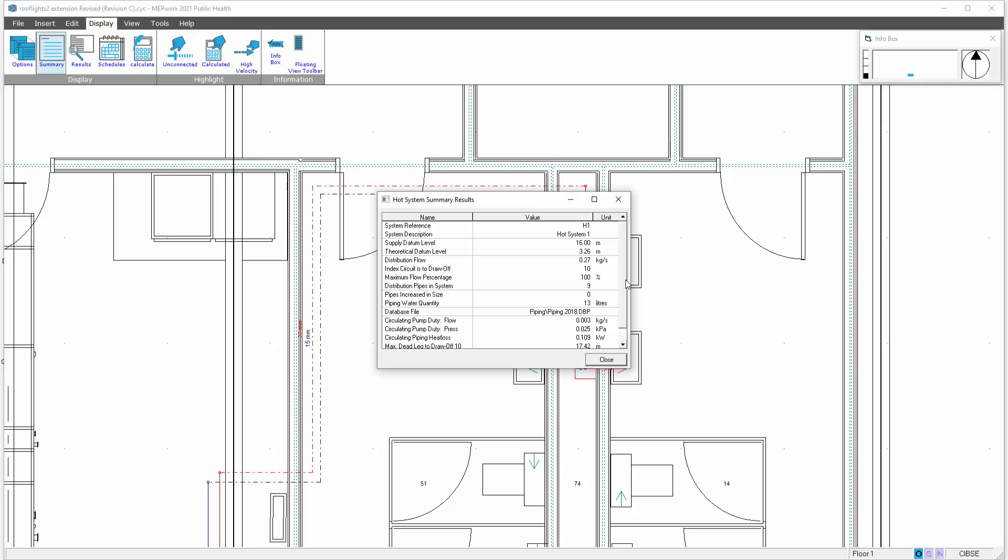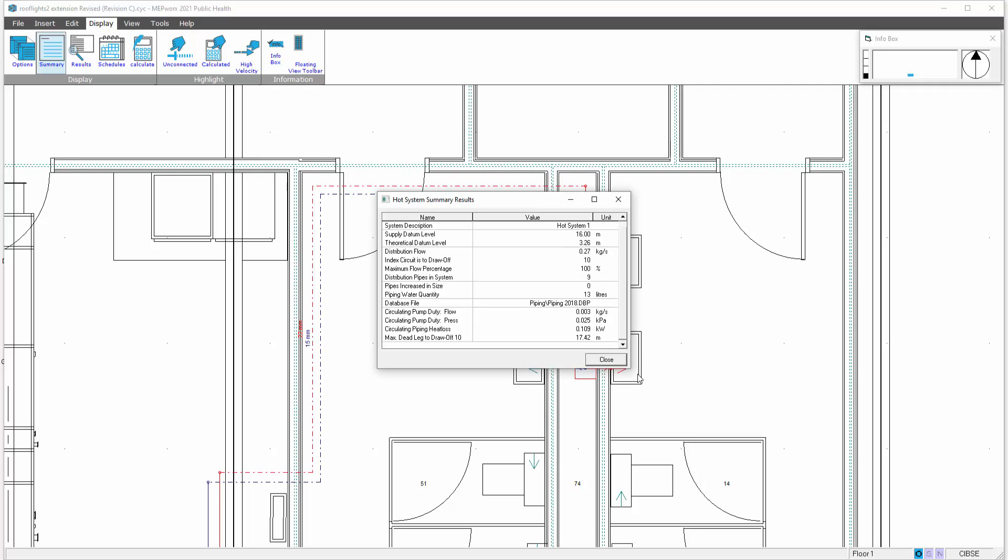Obviously this is a very small system so you wouldn't really get much of an issue here. You're only getting 0.003 kilograms a second, twenty-five pascals, and you're only getting a piping emission of just over 100 watts.